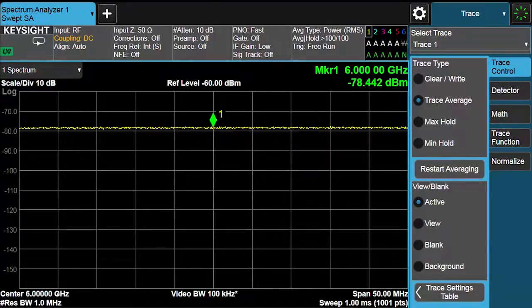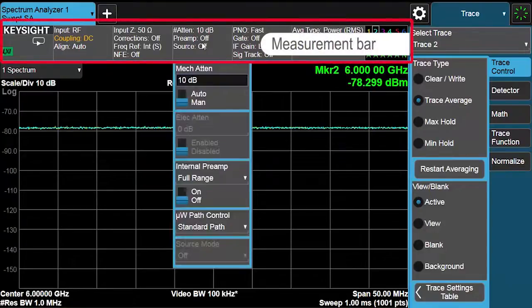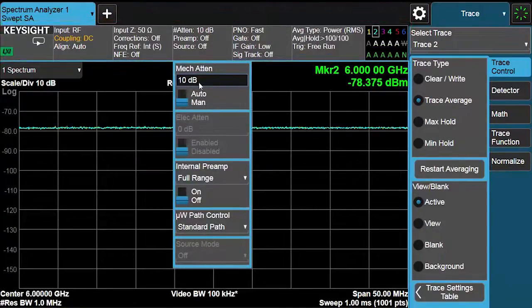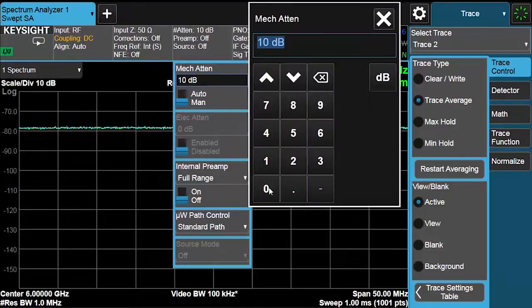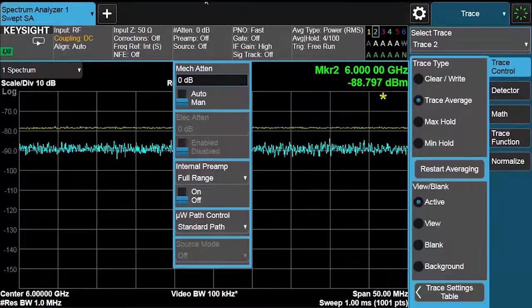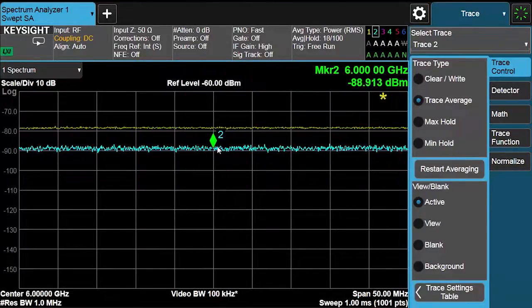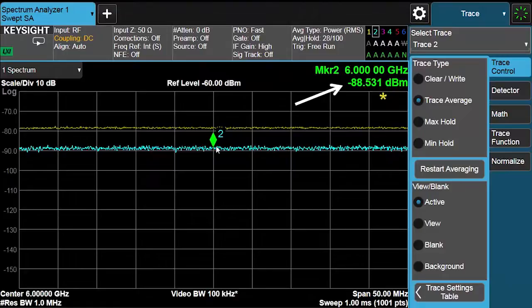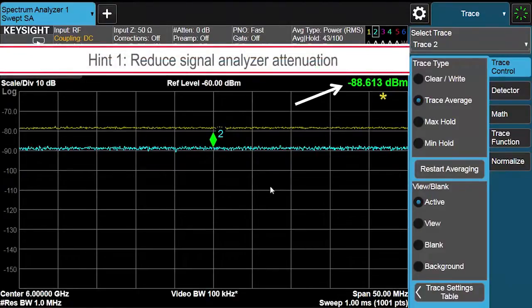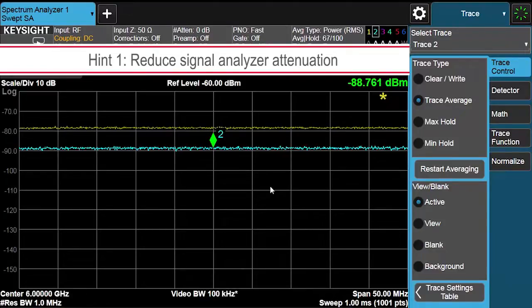First, let's see what happens when I drop the input attenuation from 10 dB down to 0 dB. I have easy access using our measurement bar to common measurement settings. My attenuation setting is here, and I'll change that to 0 dB. I've set marker two onto trace two, and we're getting a reading of minus 88 dBm. By dropping the attenuation by 10 dB, we actually will drop the noise floor by 10 dB as well. And you can see that our sweep speed is still at one millisecond.